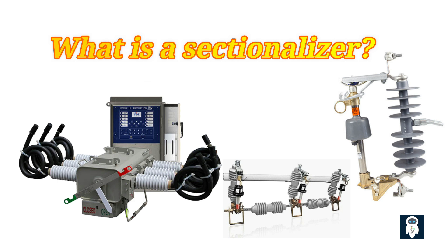they simplify the process of restoring service after a fault has been eliminated. The length of the primary line that each sectionalizer can preserve is contingent upon the value of the loads, lightning probabilities, and tree conditions. Sectionalizers can typically manage up to two or three miles of line effectively.